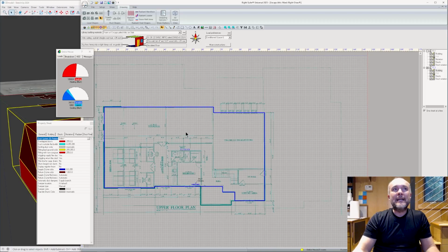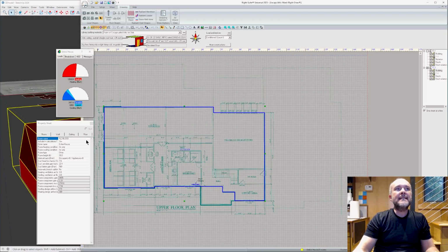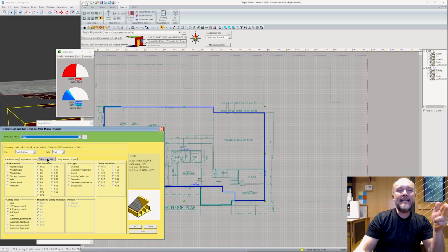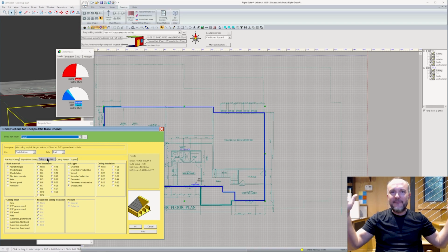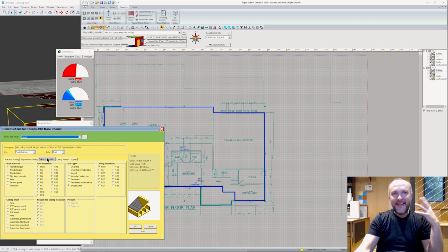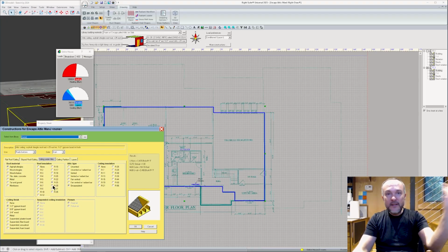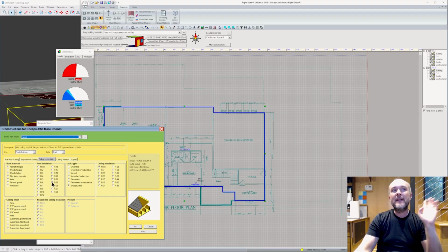When we come back here, we can see that I have, in this case, a ceiling that is ceiling under attic. And I'm imagining you guys are blowing this up to full screen so that we can see this together, but there's going to be little details that I'm pointing out. I'm going to read everything that I'm talking about here. So we've got asphalt shingles, dark in color, with an R25 in the roof deck. So between the roof rafters, there's R25 spray foam.